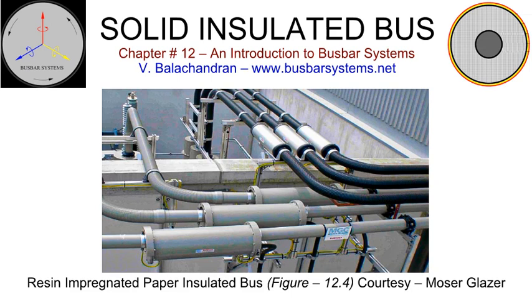Site joint assembly. Site joint assembly is the most critical subassembly. Its design differs for indoor and outdoor installation. For indoor installation, the minimum degree of protection is IP55, while for outdoor it is IP68. Further, the outdoor enclosure must withstand the effect of ultraviolet radiation, rain, snow, and erosion due to high wind velocity with dust particles. The site joint assemblies are ampacity and voltage specific. The site joints are made with laminates to cater to the expansion and contraction of the conductor due to temperature variation and minor misalignment in the axial direction during installation.